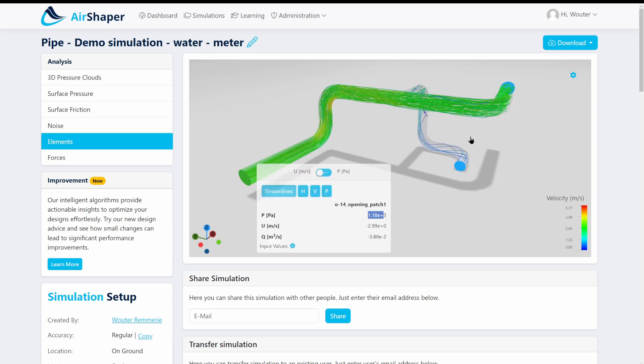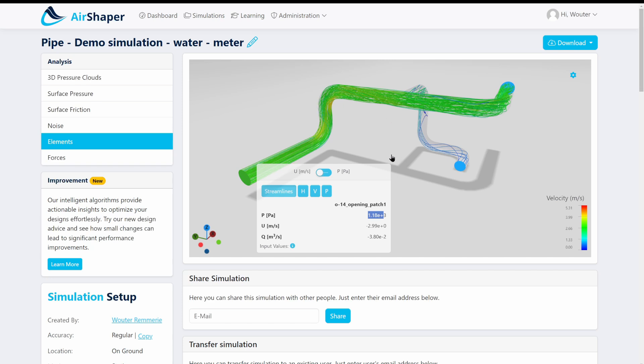So a back pressure you could say or a pressure delta across the system of 1180 pascals. So that means that's the pressure a pump would have to provide to actually push the flow at three meters per second through this pipe network. So if you want a higher velocity this would go up even further. And so on so that's really one of the key parameters that you're looking for if you're running a CFD simulation on a pipe network: the pressure drop across the entire system.